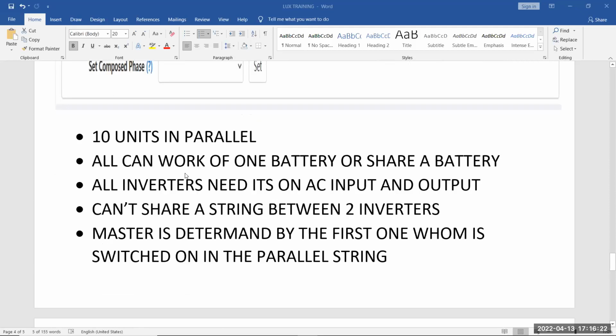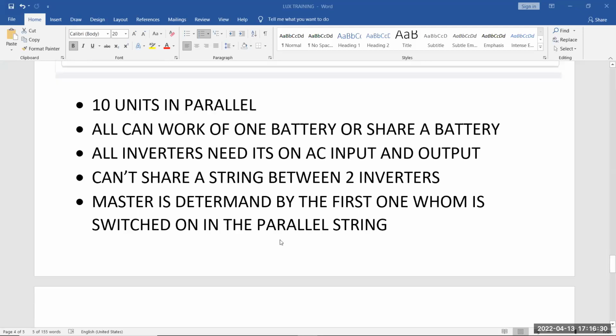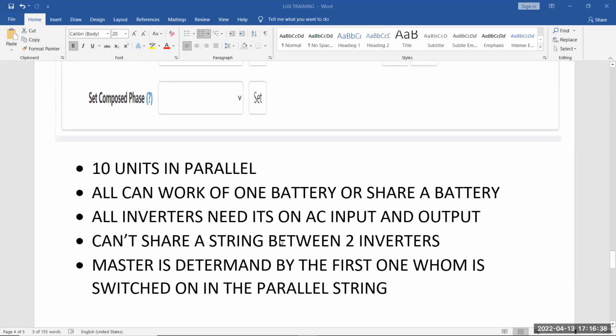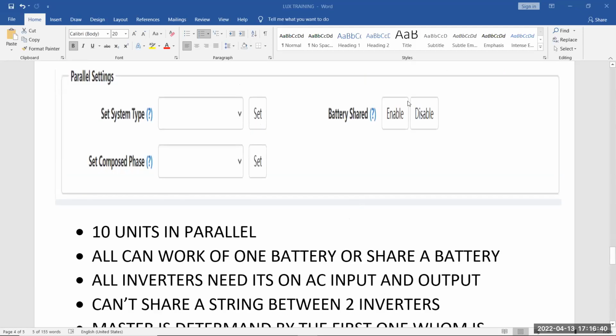Then 10 units in parallel. You can have up to 10 of my units in parallel. So that gives you a bank of 50 kilowatts of backup power of this inverter. As I said, battery shared is also enabled. So you can use one bank to supply all your inverters. Then you just have to click this battery shared enable option to tell the inverters that that's how it's working.